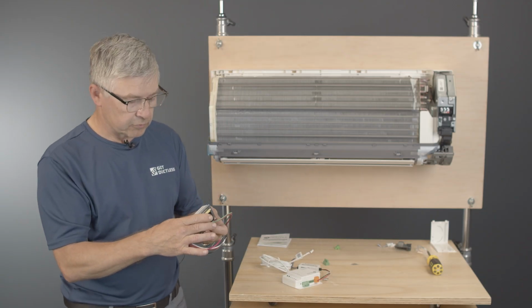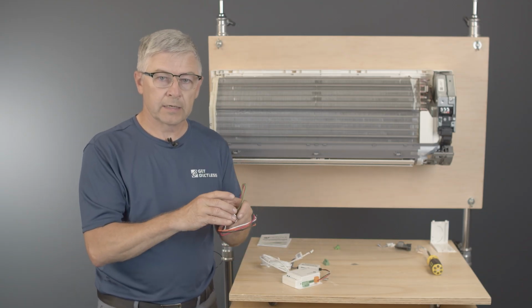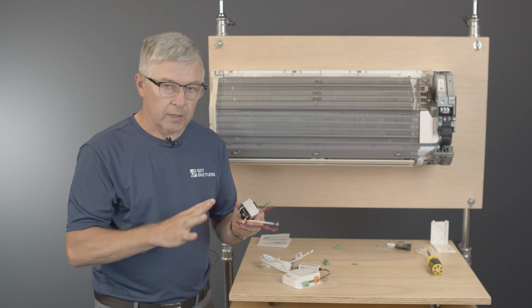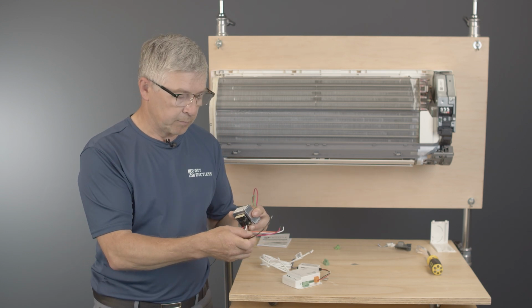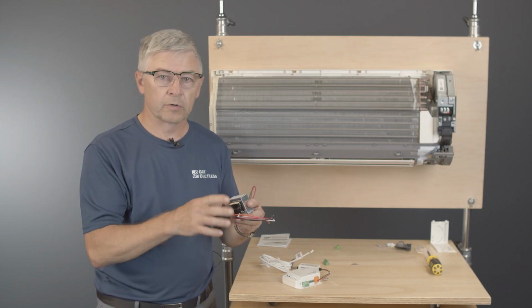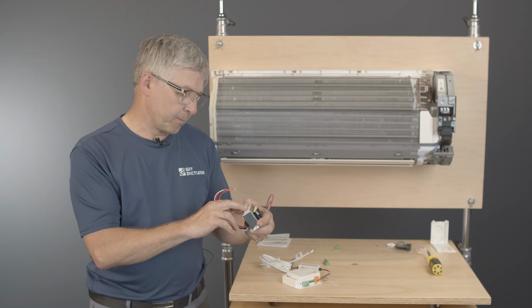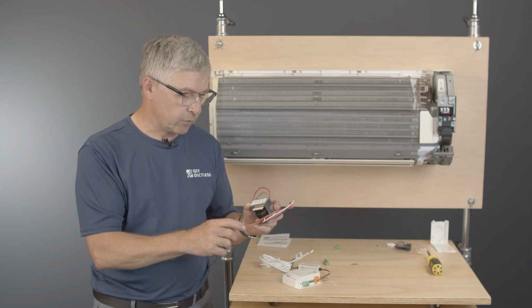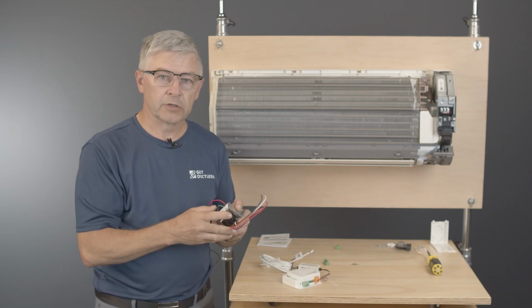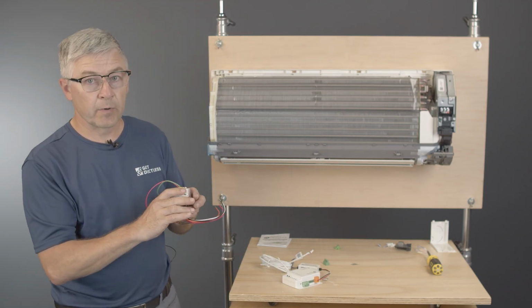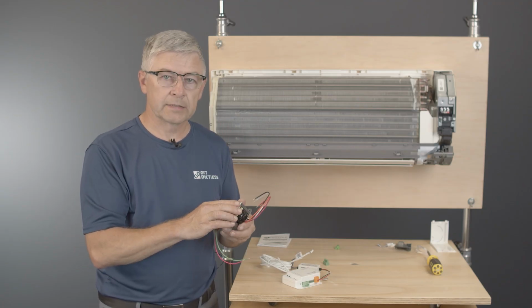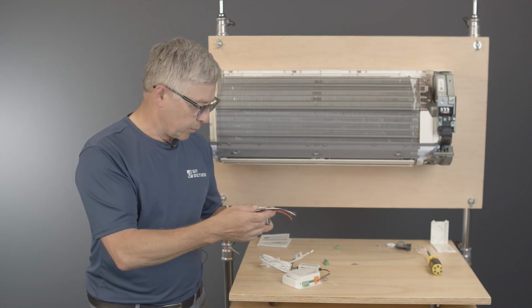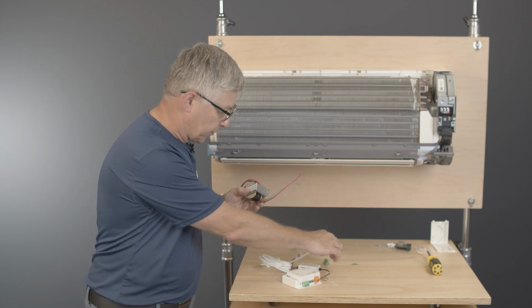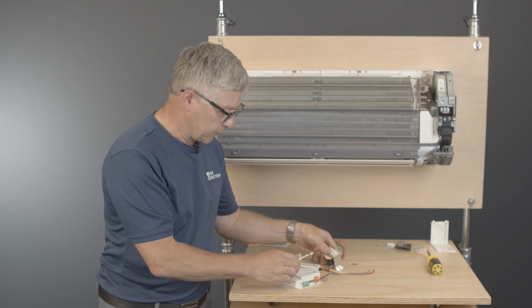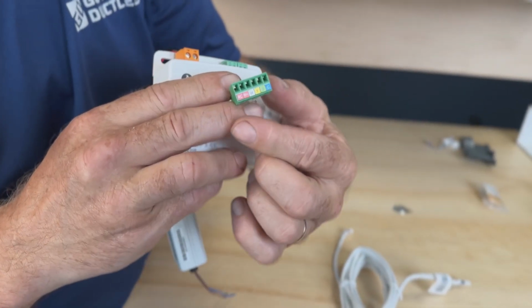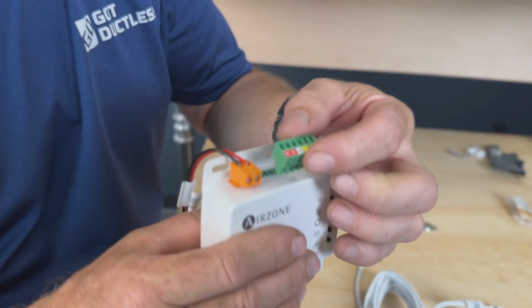Now, there's a variety of 24-volt transformers. Some could be very simple, high side, low side. Some of them will be more complicated, like this one. It can be powered by 120 volt or 208, 230, or something else. For example, this one is 120, 208, and 240, and you will be using different wires for different voltage. Again, it's highly recommended, and required in all states, to have this installed by a licensed electrician or licensed technician. So once you've connected your 24-volt side to this adapter, you just plug it in, and then you are done with this side.